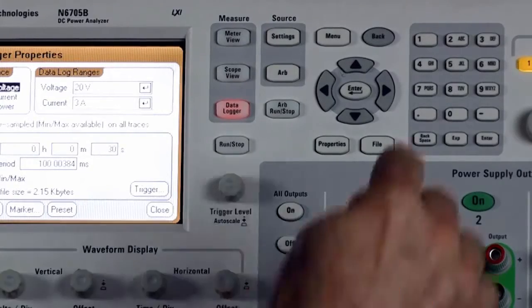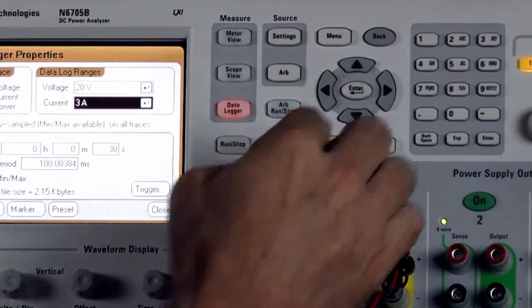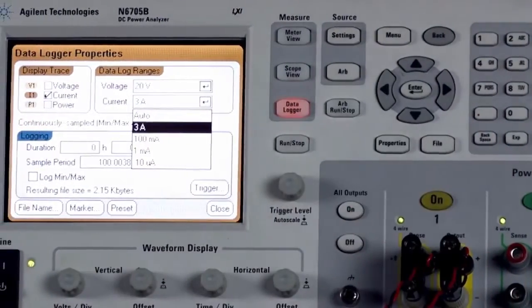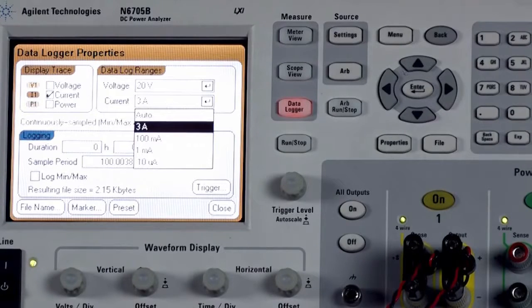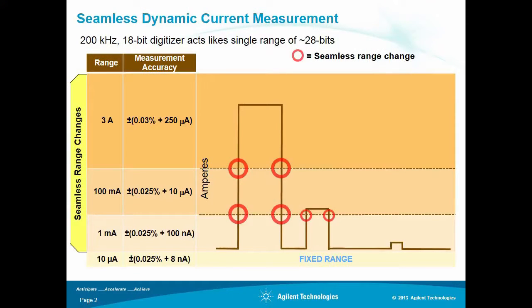The other key thing that we need to set is the current log range. As I push this, you can see we have 4 current ranges: 10 microamp, 1 milliamp, 100 milliamp, and 3 amps. If you can see on the slide, seamless auto ranging allows you to range between the 1 milliamp, 100 milliamp, and 3 amp ranges seamlessly, and that means there's no internal relay switching, there'll be no glitches. And so this allows you to dynamically look at sleep currents, which are typically in the microamp level, and up to the amp level or hundreds of milliamps when you may have some kind of an excitation current needed. This is a patented technique by Agilent and enables you to look at these dynamic currents in your medical devices.